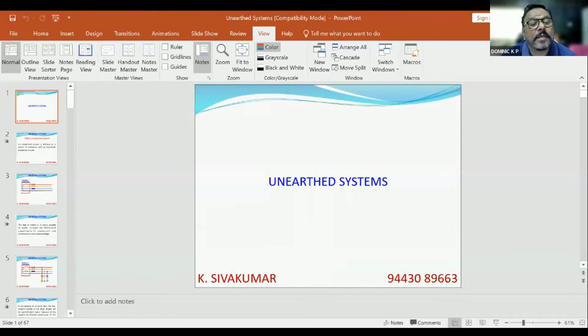Sir, Harish Maghu is asking, is the increased frequency of fire in hospitals mainly due to unearthed systems? No, definitely not. Fire is a matter of heat, which is a matter of current. In an unearthed system, the earth fault current is negligible. There are other reasons. I would rather say it could be a phase-to-phase short circuit in an unearthed system, or a phase-to-ground short circuit in an earthed part of the hospital network.